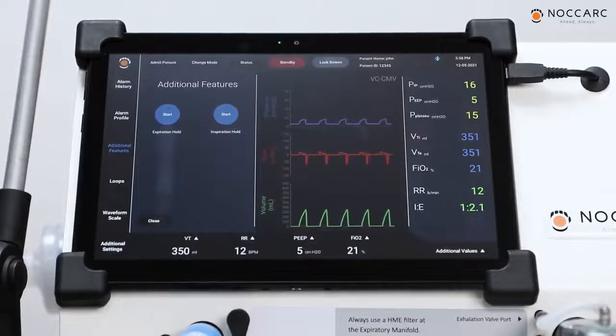Inspiration hold simulates the condition of simultaneous closing of inspiration and expiration valves. It extends the inspiratory phase of single mandatory breath for the purpose of measuring plateau pressure and lung compliances. Pressure on either side of the artificial airway is allowed to equilibrate, which determines the pressure during no flow state.